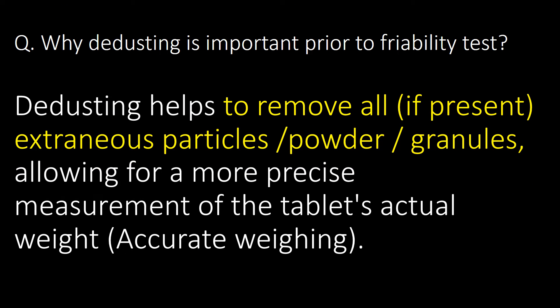Why is de-dusting important prior to the friability test? De-dusting helps to remove all extraneous particles, powder, and granules, allowing for a more precise measurement of the tablets — giving the actual weight, i.e., accurate weighing is possible after de-dusting.